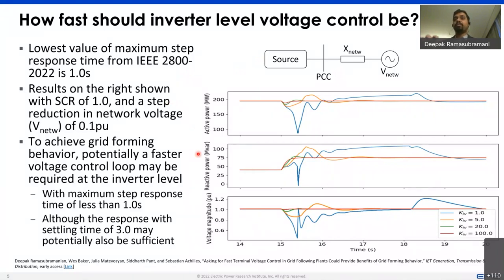Now, some of this might be inherently embedded into other types of control techniques for grid forming, but the property that is coming out is this fast voltage control, and that is what we want to recognize, because once we recognize that this is the property, we can derive specifications around it. So for an example here, we say that the step response time, the settling time here, should be less than 1 second, and that can enable the stability of the system in this low short circuit environment. And there are a few links to some publications that can provide a little bit more insight on that.